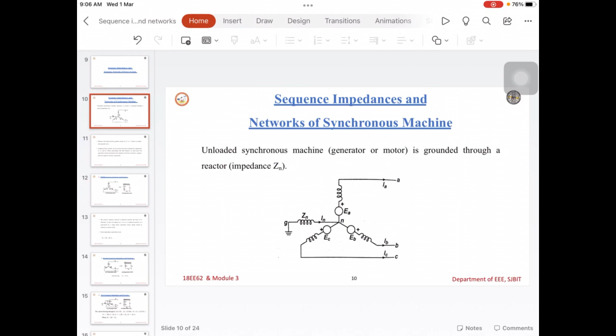Next we consider the positive, negative and zero sequence network representation for the synchronous machine. An unloaded synchronous machine is grounded through a reactor. Here we consider the equivalent circuit of the three-phase generator. Each phase, A phase, is represented by its induced voltage along with the reactance of the A phase winding, and similarly for B phase and C phase, all three connected in star fashion with the neutral grounded through the reactance.